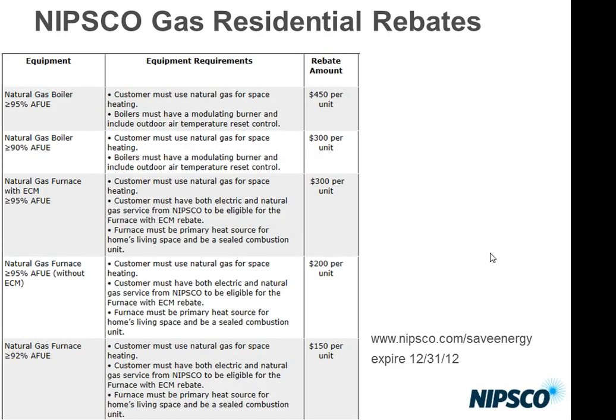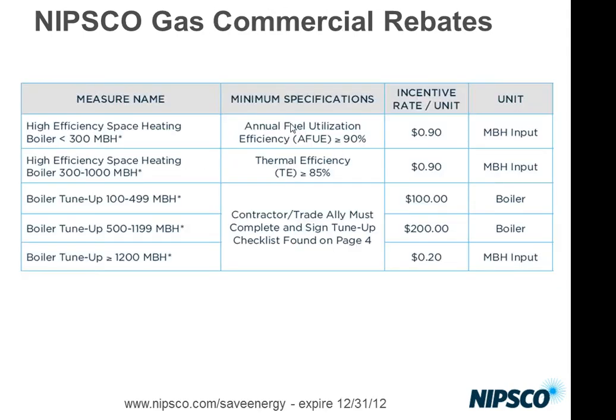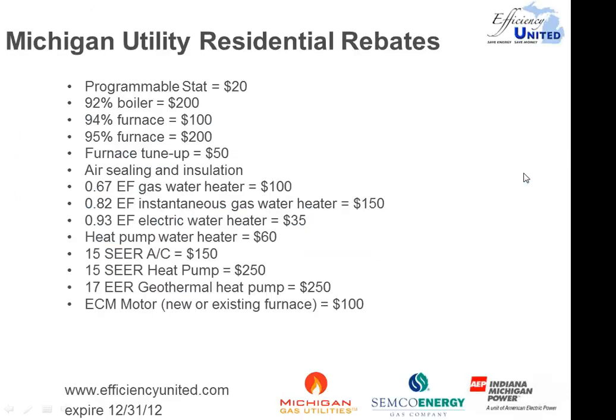If you're out in Indiana, residentially speaking, the boilers are same tiers as we have in Illinois, 90 and 95%, corresponding to $300 and $450 rebates. And once again, you have to have outside air reset controls to get those rebates, which lends themselves very well to radiant systems. If it's a commercial building with a larger boiler, it's basically tiered on how big the boiler is, but the typical commercial boiler under 1 million BTUs in size, it's 90 cents for every MBH in terms of boiler size, and all these are based on boiler input sizes.